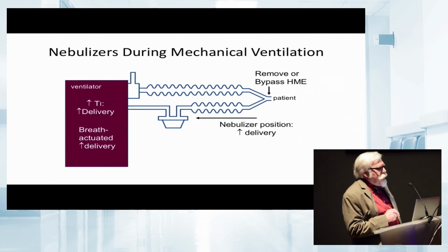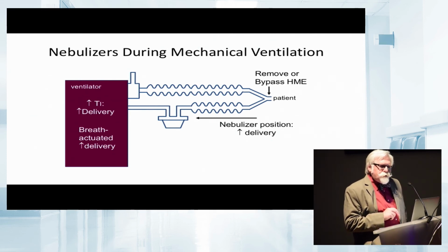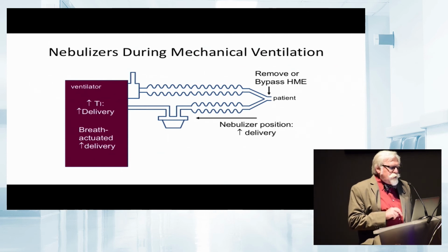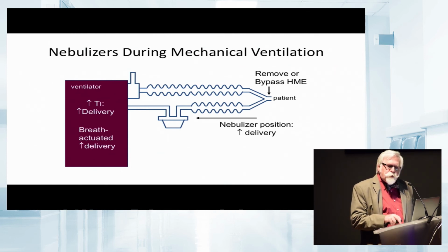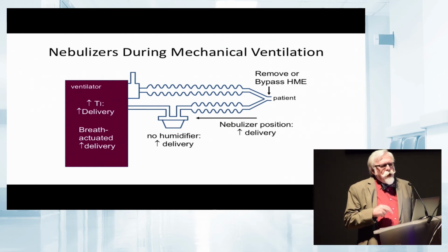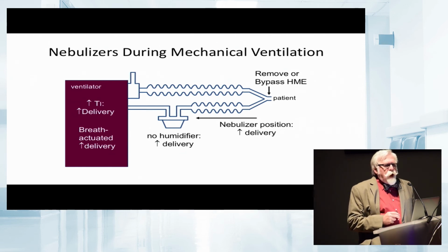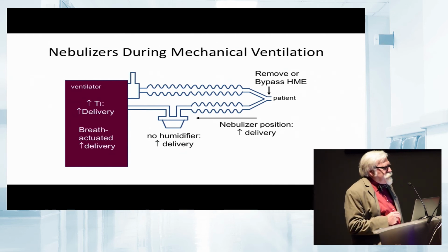If we move the nebulizer further away from the patient and closer to the ventilator, that increases the amount of aerosol delivery. If we deliver the aerosol into a dry gas, in other words, take the humidifier out of the circuit, that will increase the aerosol delivery. However, I do not recommend that because it will have a drying effect on the lower respiratory tract of the patient.